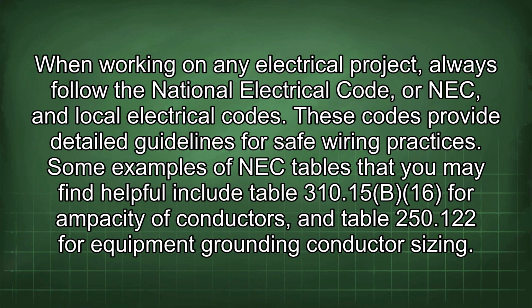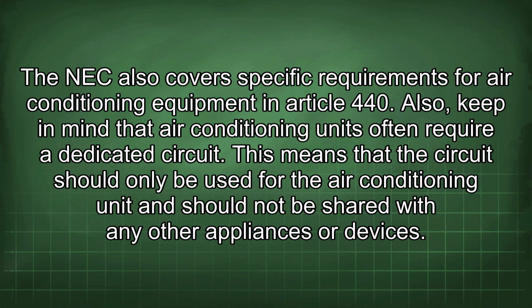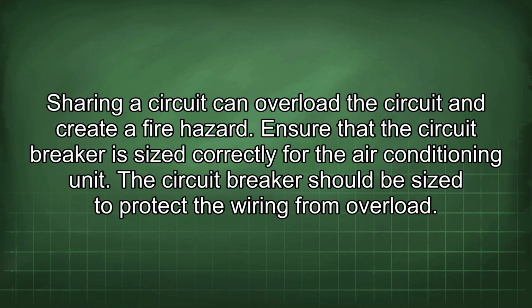Some examples of NEC tables that you may find helpful include Table 310.15(B)(16) for ampacity of conductors, and Table 250.122 for equipment grounding conductor sizing. The NEC also covers specific requirements for air conditioning equipment in Article 440. Also, keep in mind that air conditioning units often require a dedicated circuit. This means that the circuit should only be used for the air conditioning unit and should not be shared with any other appliances or devices. Sharing a circuit can overload the circuit and create a fire hazard.